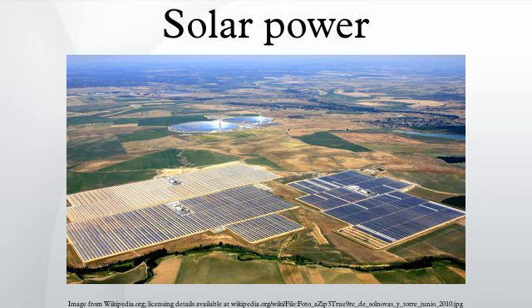Self-consumption. In cases of self-consumption of the solar energy, the payback time is calculated based on how much electricity is not purchased from the grid. For example, in Germany, with electricity prices of €0.25 per kWh and insolation of 900 kWh/kW, 1 kWp will save €225 per year, and with an installation cost of €1,700 per kWp, the system cost will be returned in less than 7 years. However, in many cases, the patterns of generation and consumption do not coincide, and some or all of the energy is fed back into the grid. The electricity is sold, and at other times when energy is taken from the grid, electricity is bought. The relative costs and prices obtained affect the economics.